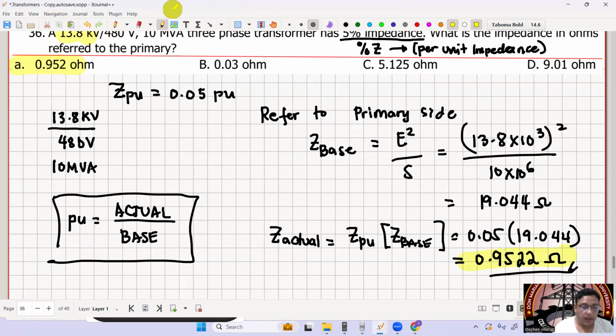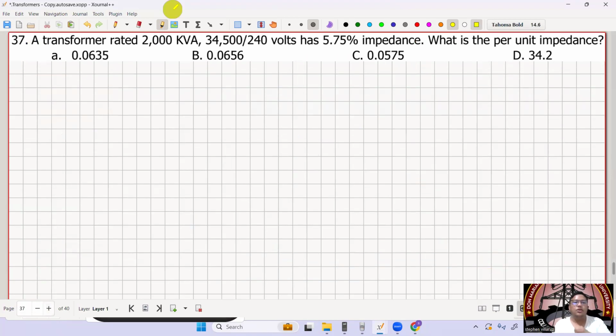Okay? Next, number 37. So, a transformer rated 2000 kVA, 34,500 slash 240 volts has 5.75% impedance. What is the per unit impedance? So, kakasabi ko lang sa inyo, kung ano yung percent impedance, yun na rin yung per unit impedance. So, therefore, the answer is 0.0575.